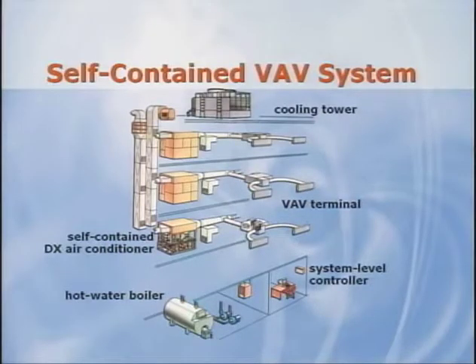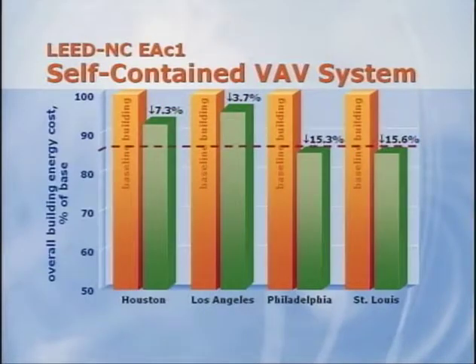Sure, John. In many ways, a self-contained VAV system is similar to rooftop VAV, except that the packaged DX units are located indoors, typically in a small mechanical room on each floor of the building. Also, they contain water-cooled condensers, which are piped to a cooling tower. Here's the chart comparing the proposed building with a self-contained VAV system to the same baseline building, which, as you recall, has a chilled water VAV system.